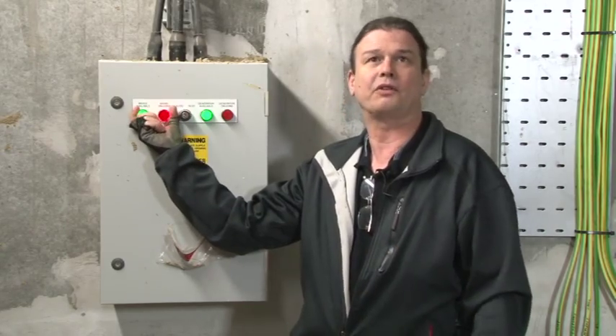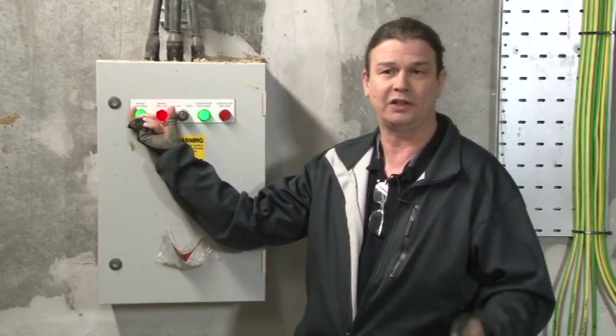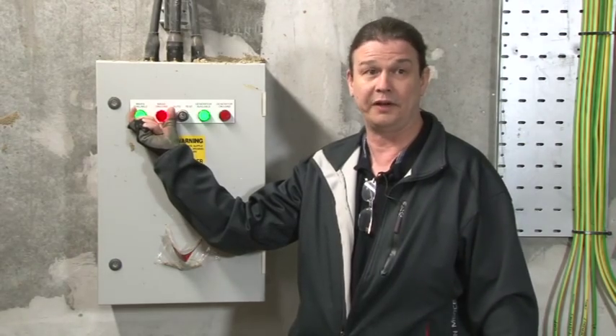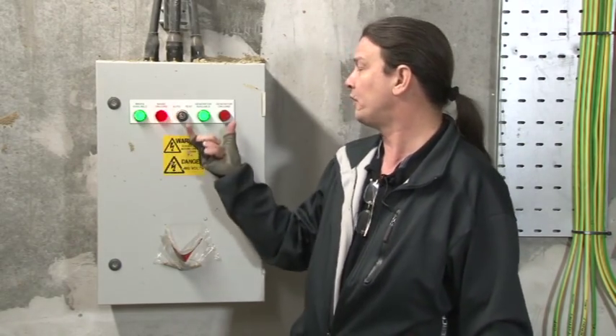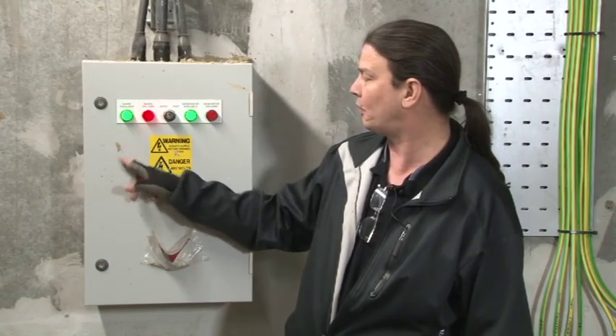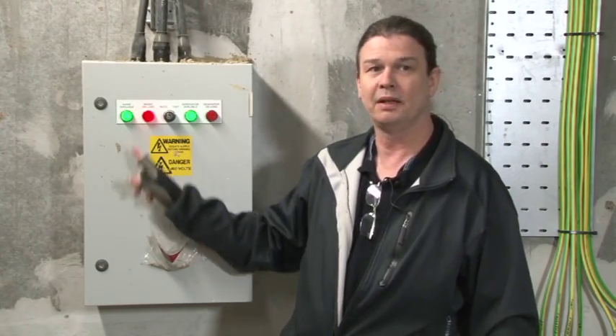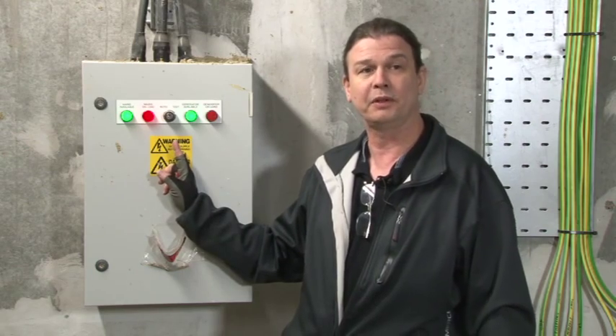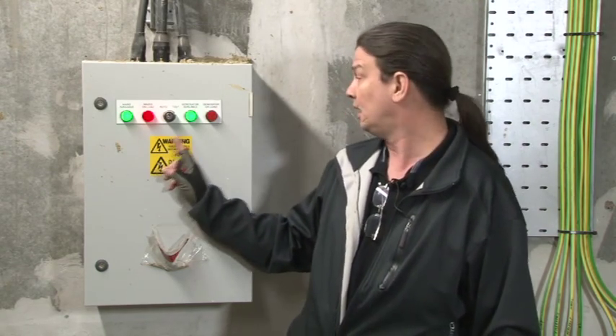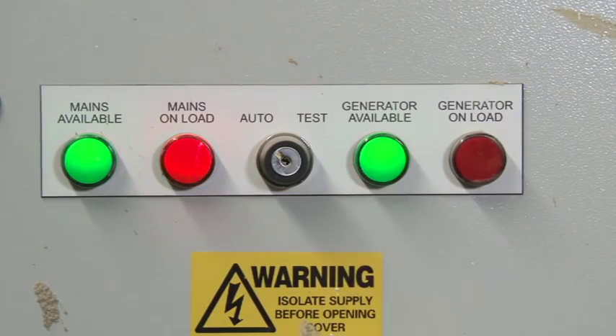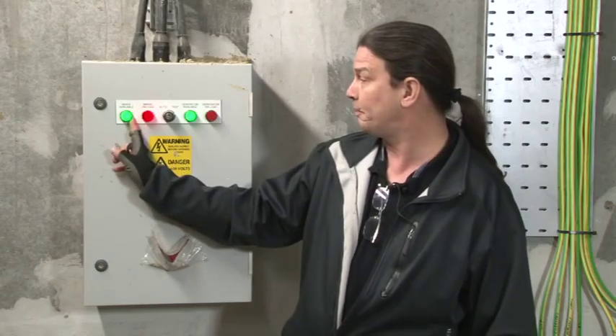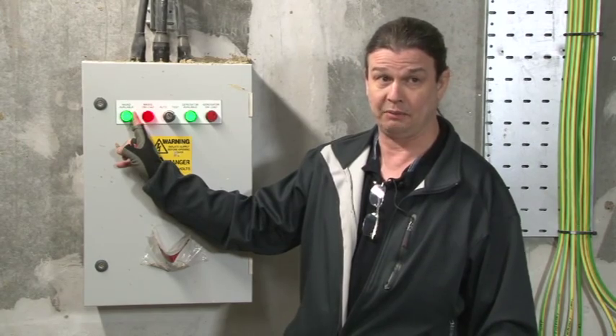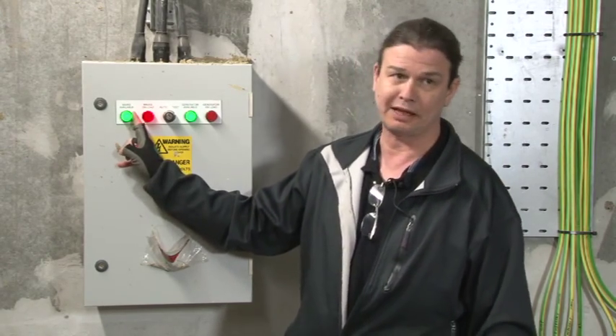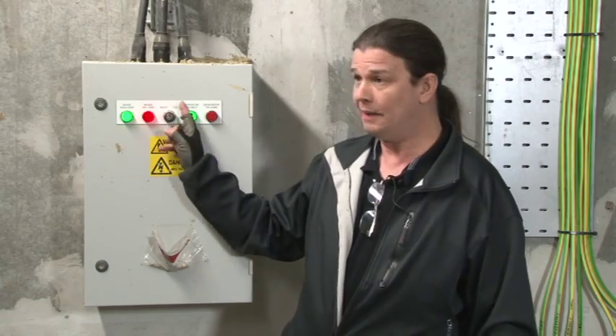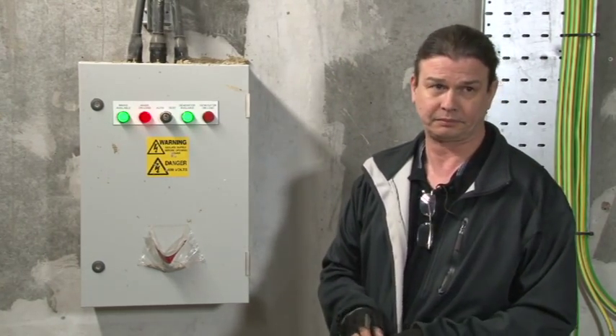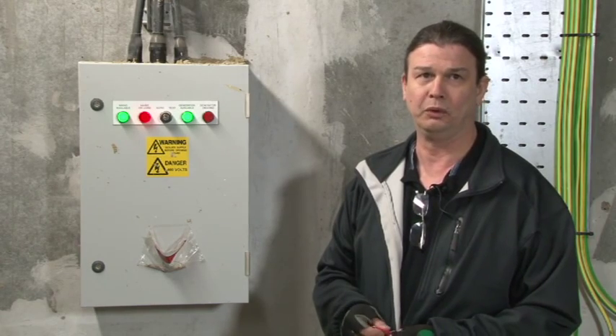In the event that, for example, a fire has rendered the primary supply unavailable, the sensor inside here says, right, that supply is no longer available to me. Because it's a live fire safety system, because the fireman's lift has to work in the event of a fire, it will then switch to the secondary system. It's fully automatic. Once the primary supply has been re-energised, it will flip back automatically, should the cable be suitable to do so. The cables are fire-rated cables, so they stand up to an awful lot of fire before they melt through.